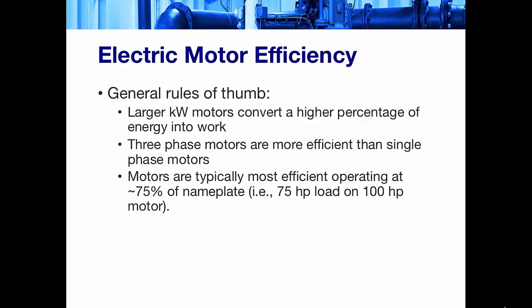On the next slide, we talk about motor efficiency. General rules of thumb: the larger the horsepower or kilowatt rating, the better the motor is at converting energy into work, so they're more efficient. 3-phase motors also typically are more efficient than single-phase motors, but single-phase motors in most applications are going to be relatively low horsepower, maybe 2 horsepower or so at the most. So most of your larger pumps and things like that are going to be 3-phase.